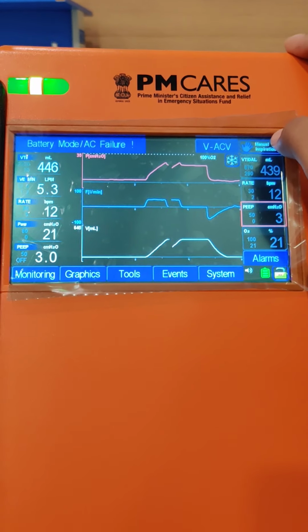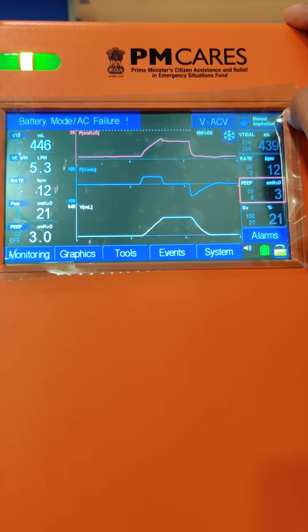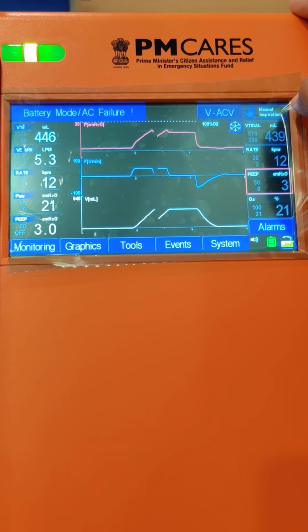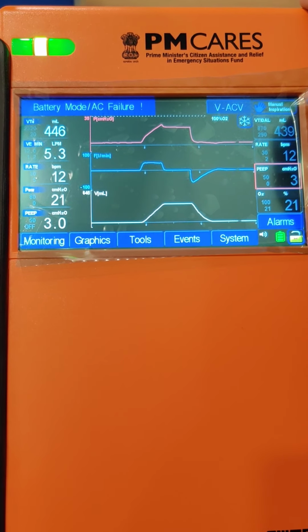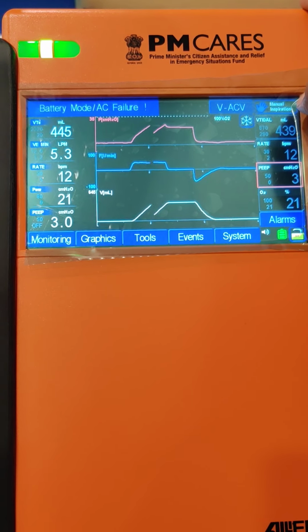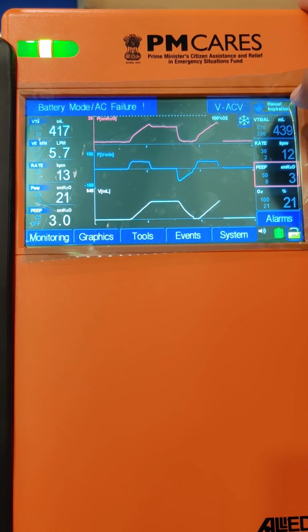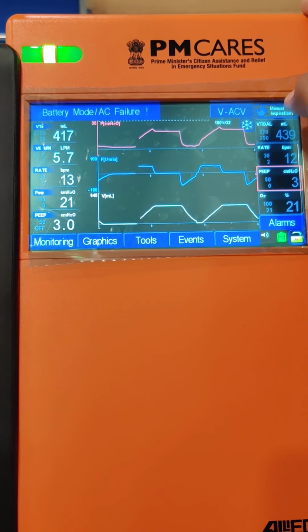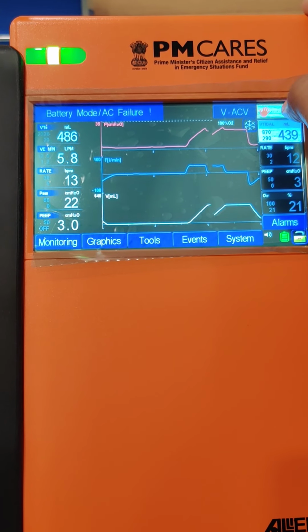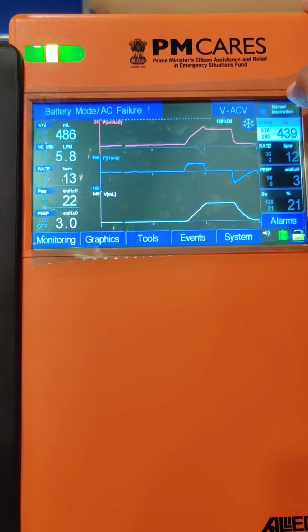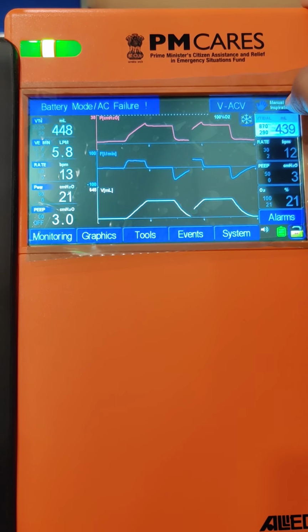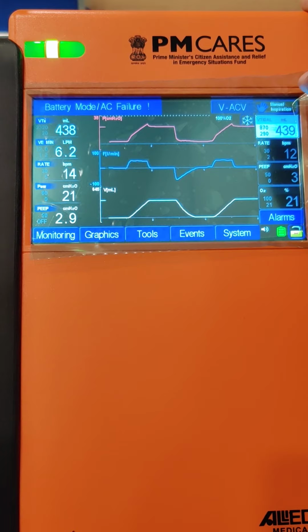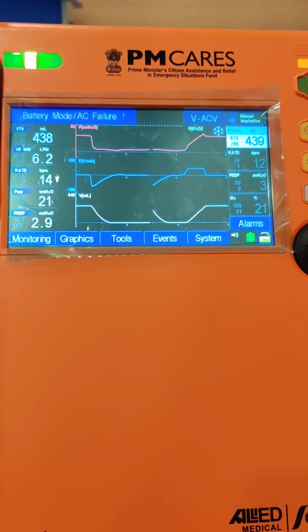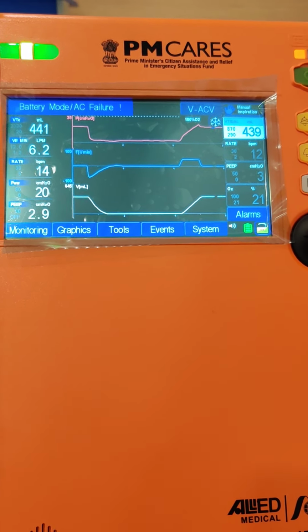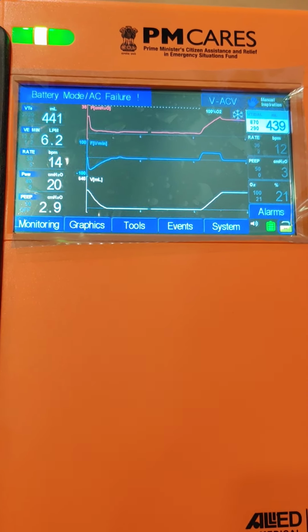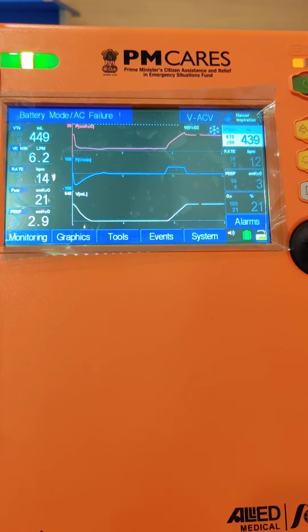Over here we have given one manual inspiration button. If you have set the ventilation at 12 bpm, and in between you want to give any emergency breaths to the patient of the same volume, then whenever you press this manual inspiration, the whole breath will be given to the patient. So in any emergency case, if you want to give mandatory breaths in between the settable breaths, you can use this manual inspiration button.